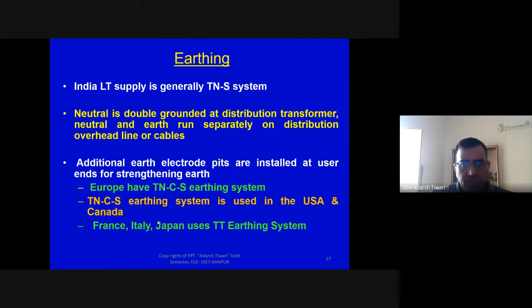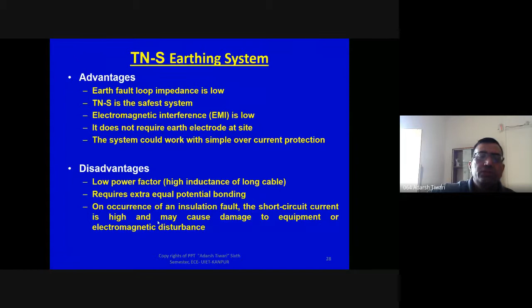If we see the advantages of what we have adopted in India, the TN-S system: the earth fault loop current is low. It is safer. EMI, which is electromagnetic interference, is low. It doesn't require an earth electrode at site, and the system could work with simple overcurrent protection. That means we only have to install overcurrent protection. And what are the disadvantages? It has a low power factor, requires extra equipotential bonding, and on occurrence of an insulation fault, the short circuit current is high, and it may damage the equipment, or the EMI, electromagnetic disturbance, will increase.